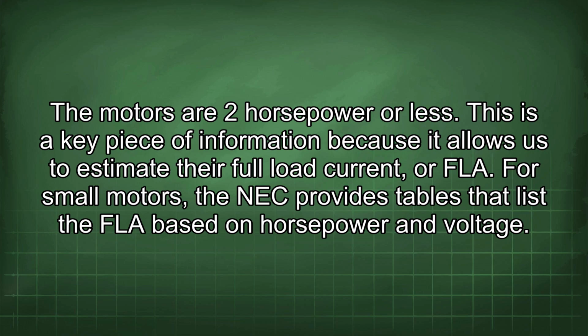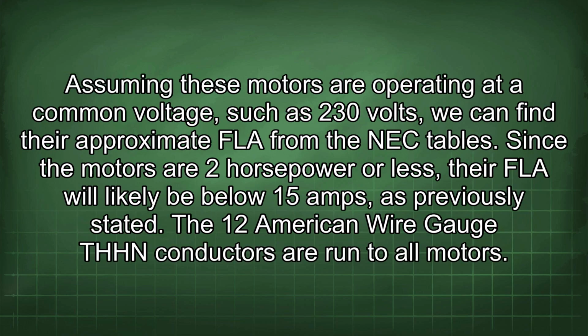The motors are 2 horsepower or less. This is a key piece of information because it allows us to estimate their full load current, or FLA. For small motors, the NEC provides tables that list the FLA based on horsepower and voltage. Assuming these motors are operating at a common voltage, such as 230 volts, we can find their approximate FLA from the NEC tables. Since the motors are 2 horsepower or less, their FLA will likely be below 15 amps, as previously stated.